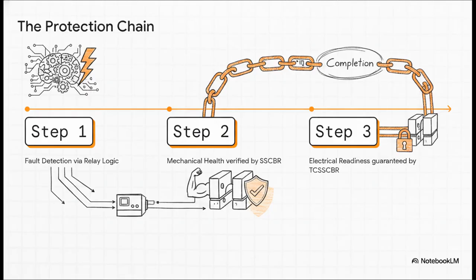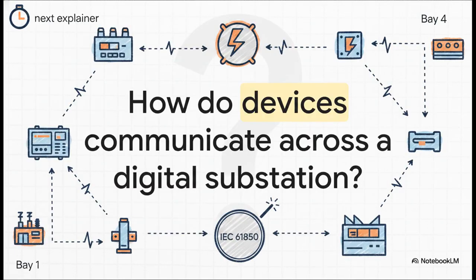And this brings our local protection chain to a true state of completion. Step 1. The relay logic flawlessly detects the fault. Step 2. The SSCBR function has already verified the breaker's mechanical health is solid. Step 3. The TCSSCBR function guarantees the electrical pathway is perfectly ready to deliver the message. We have successfully secured every single link, from the digital brain inside the relay all the way down to the physical copper wire attached to the breaker. So we've got an incredibly robust, self-diagnosing, highly secure local bay.